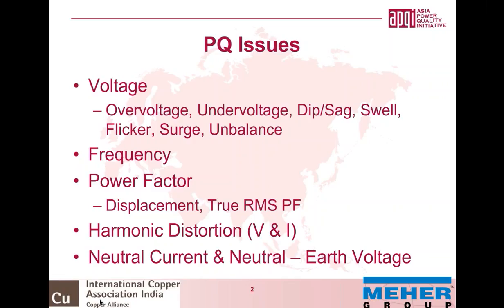Mathematically, all these triplen harmonics add up in the neutral, and therefore it is possible that the neutral current can become similar to the phase current, or in many cases even exceed the phase current. So we have to be a little careful and manage this properly. With regard to the neutral, another important aspect is the neutral to earth voltage, because in many protection systems and in many sophisticated systems, this value has to be below a certain level, and if it is not below that level, it can create negative side effects for the whole system.